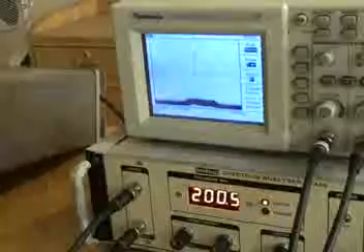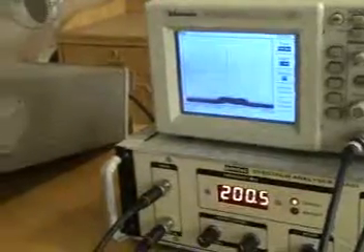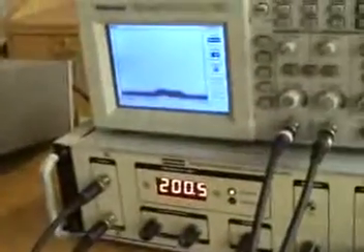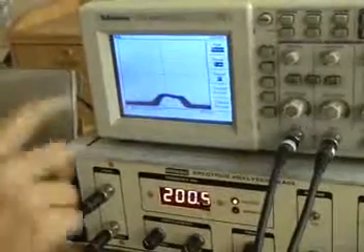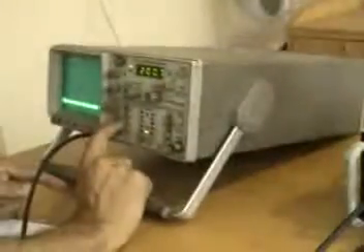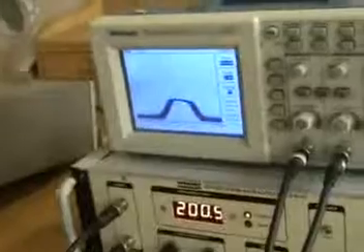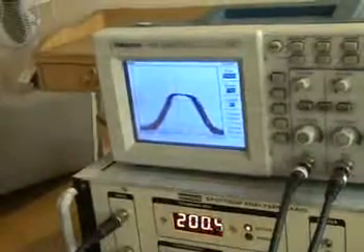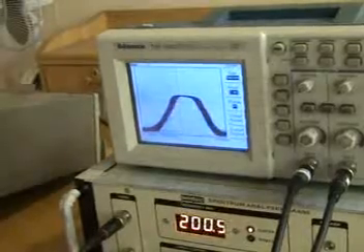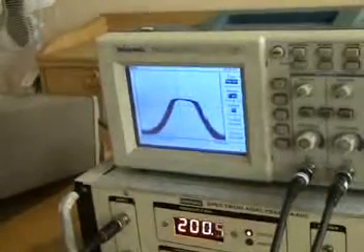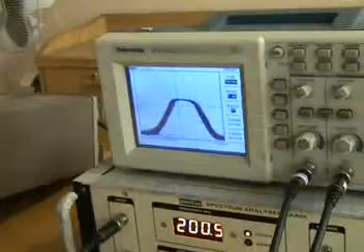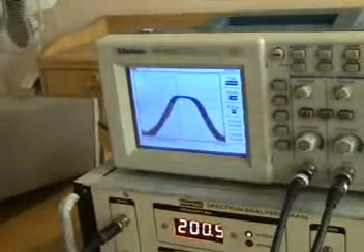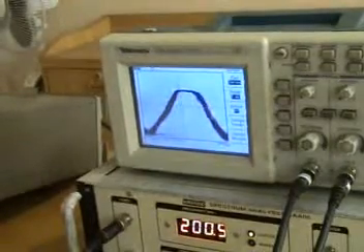Now once again we are showing that if we increase the amplitude by 10 dB here, the signal has been increased by 10 dB, further 10 dB, like that. So right now you are seeing a signal of minus 57 dBm. This is a variable control pot. You can see the 10 dB it is increasing.